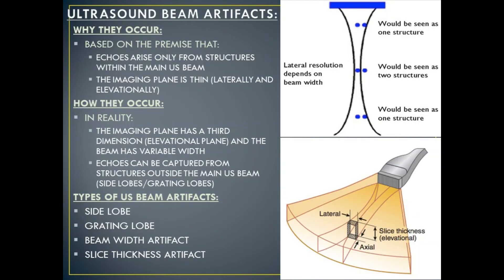Our first category of ultrasound artifacts are ultrasound beam artifacts. These occur because ultrasound is based on the premise that echoes arise only from structures within the main ultrasound beam, and the imaging plane is thin both laterally and elevationally. In reality, the imaging plane has a third dimension — the elevational plane — and the beam has a variable width. Echoes can be captured from structures outside the main ultrasound beam. Types of ultrasound beam artifacts are side lobes, grating lobes, beam width artifacts, and slice thickness artifacts.